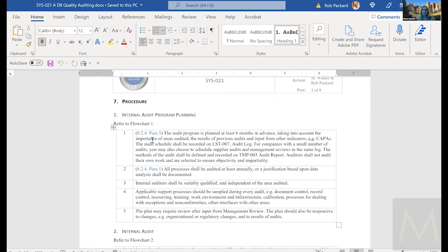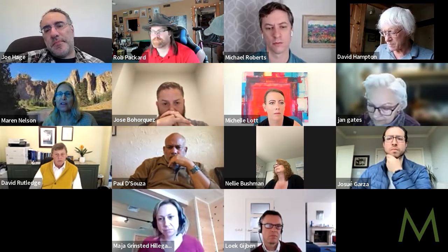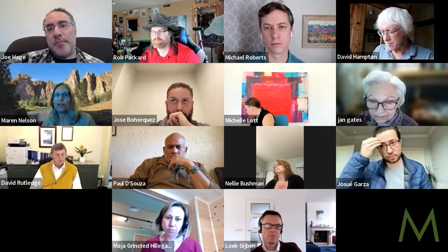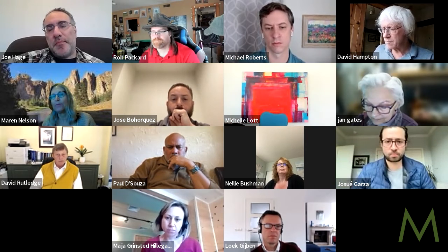And then just in the background, the regulatory people can go through and make sure all the details are checked. And I find updating those tables, like if you go from one version of 13485 to the next version of 13485, it's pretty easy to do the gap assessment then, because I've got all the traceability to what's there and what's been created. If you're adding a new country, then you can look at their regulations and go, oh yeah, it's the same requirement. I've already got it covered in these procedures. So it's similar to what you're doing in the internal audit, but like Michelle, I do it as a separate.